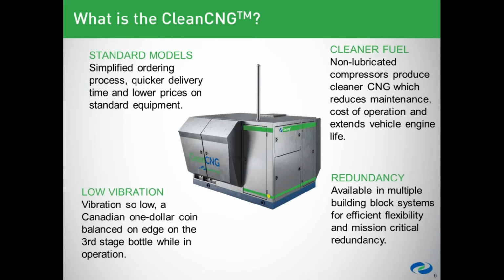We needed to obviously focus on the cleanest possible end-user product, the natural gas itself. And so we have done advancements in ring design on our non-lubricated platform. Redundancy was another key area of focus, allowing you to literally Lego block these units together. So the platform itself, the photo you're seeing there, you can take those end panels off. The end panels of the adjacent unit are taken off. They're put proximate to each other. A bridging kit is put there, and all airflow as well as maintenance access is fully maintained because that's the way the unit's being designed.